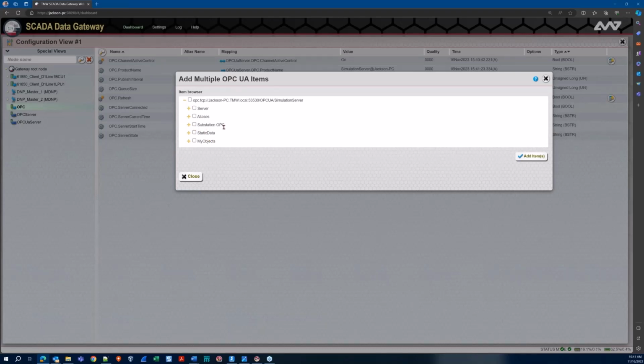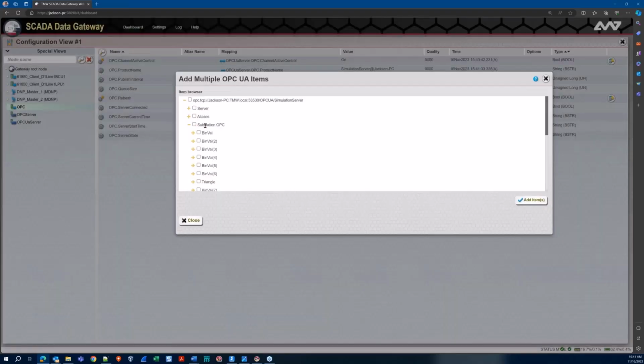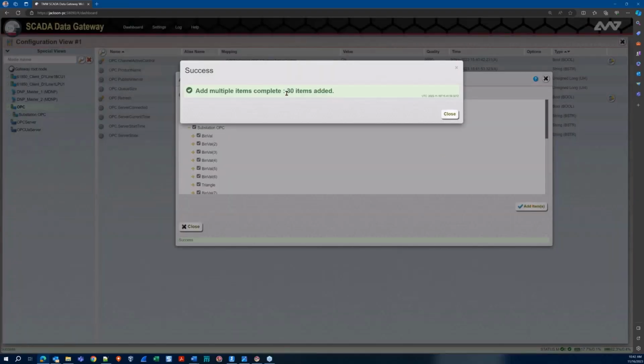In this case, on my OPC server created just for this demo, I made a folder called Substation OPC that has a bunch of different data in it, including an object called voltages that itself contains 10 children elements named voltage 1 through voltage 10. So I created it for the purpose of adding it all to my OPC client. I'll just go ahead and check all and say add items. Sure enough, it has added the 30 items that I created.